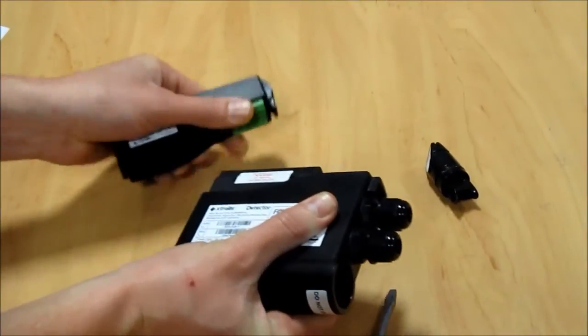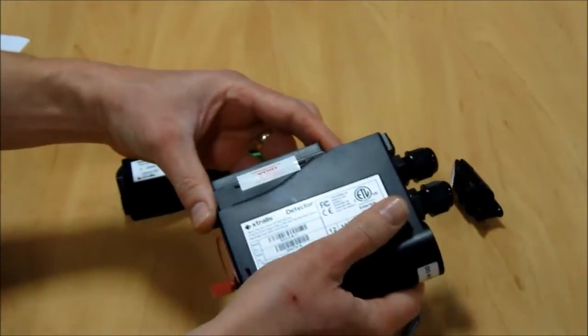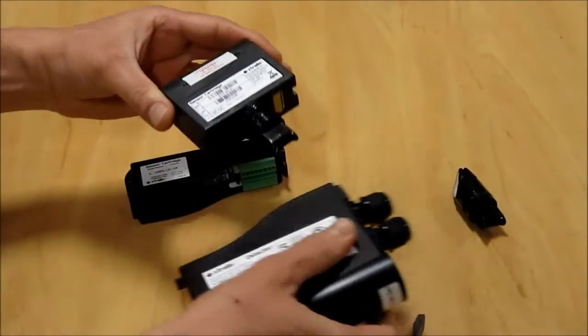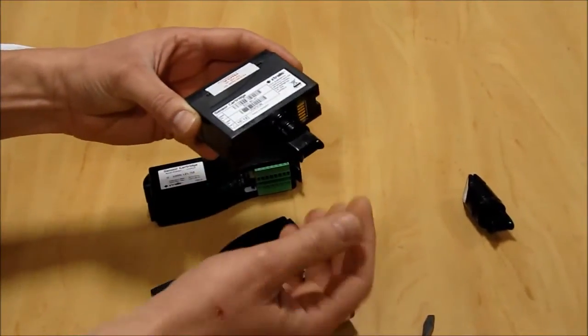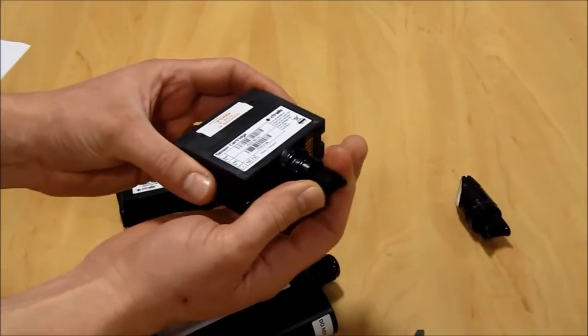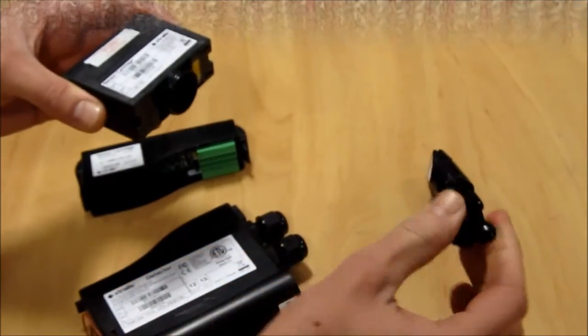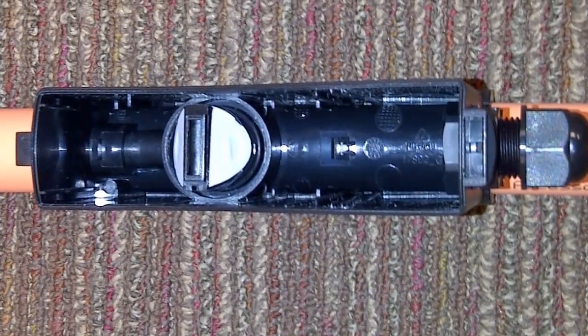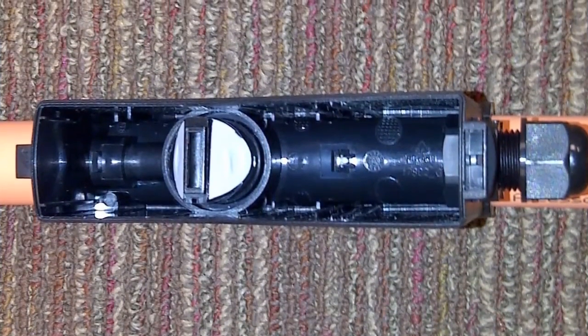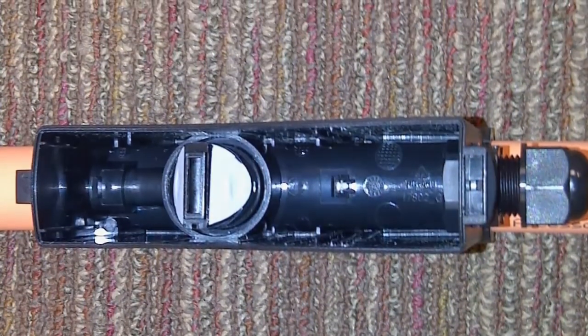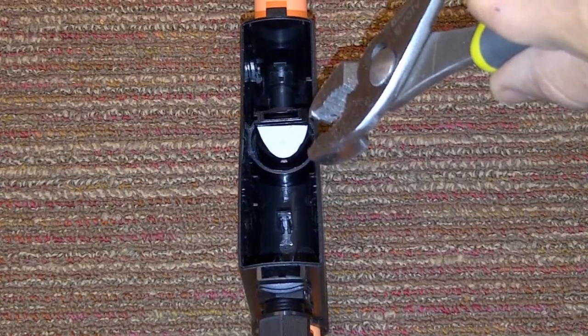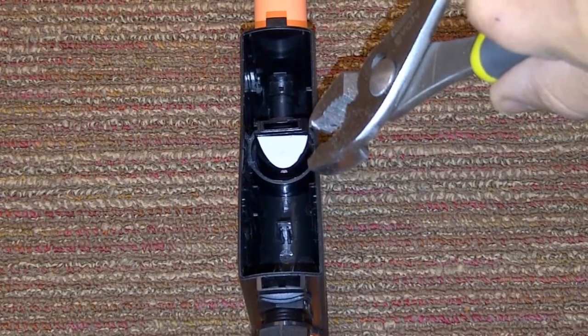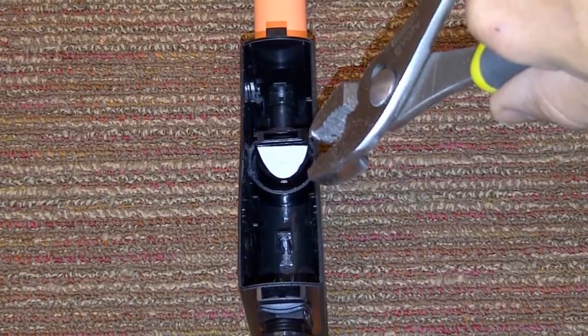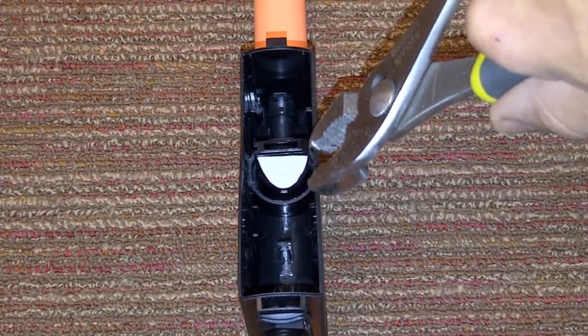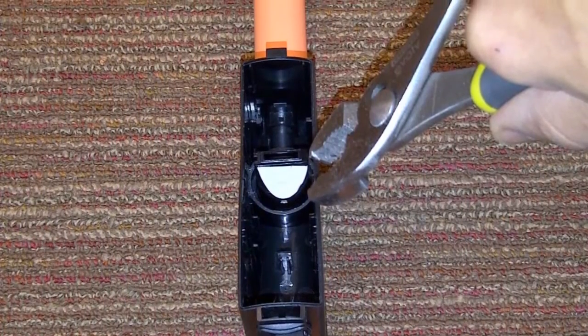With the lid removed, remove the sensor cartridge by pulling it straight out, and then pull the filter cartridge assembly from the sensor cartridge. Some force will be needed. If the filter assembly remains in the body and it's not on the pipe, push it out from behind. Otherwise, a tool may be needed to remove the filter from the detector. The filter will be damaged, but it is to be replaced.